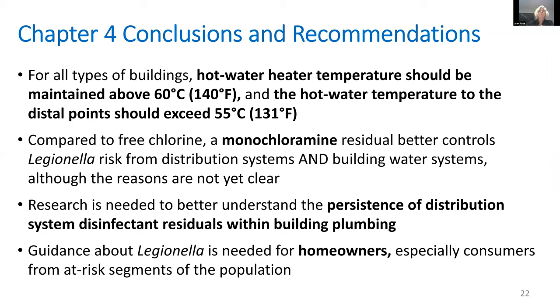Chapter 4 recommends that for all building types, hot water heater temperature should be maintained above 60 degrees C, 140 degrees Fahrenheit, and the hot water temperature to the distal points, not to the fixtures, should exceed 55 degrees C, 131 degrees Fahrenheit.